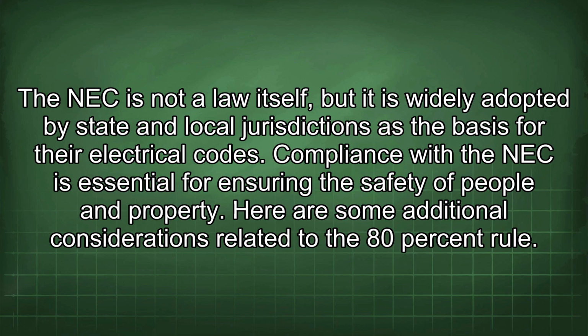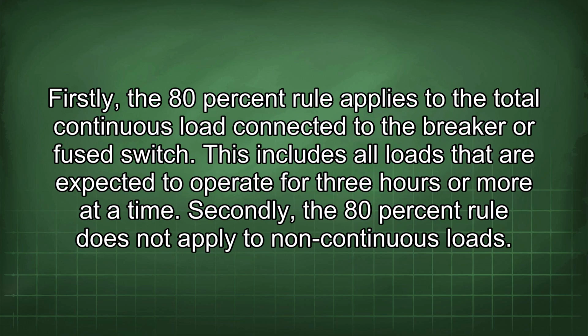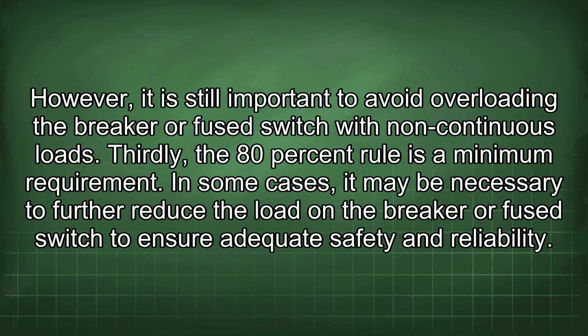Here are some additional considerations related to the 80% rule. Firstly, the 80% rule applies to the total continuous load connected to the breaker or fuse switch. This includes all loads that are expected to operate for 3 hours or more at a time. Secondly, the 80% rule does not apply to non-continuous loads. However, it is still important to avoid overloading the breaker or fuse switch with non-continuous loads.